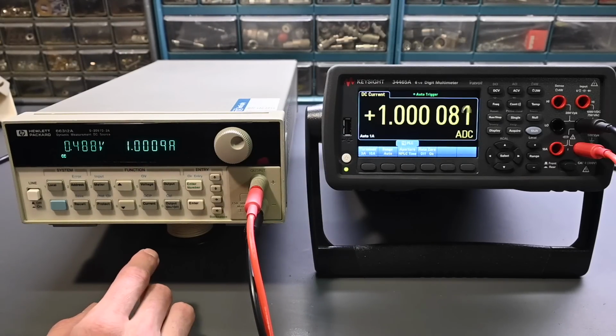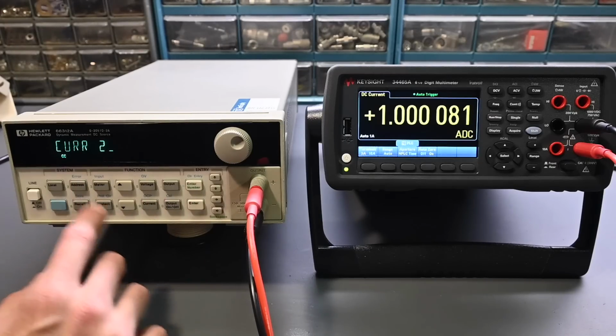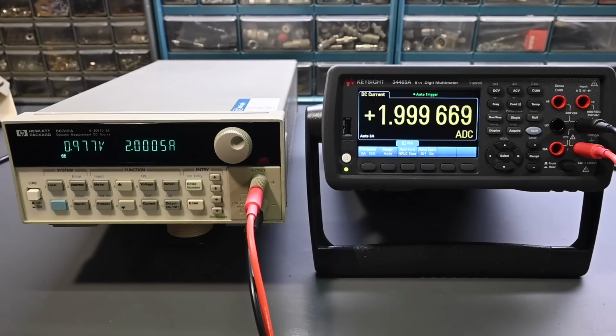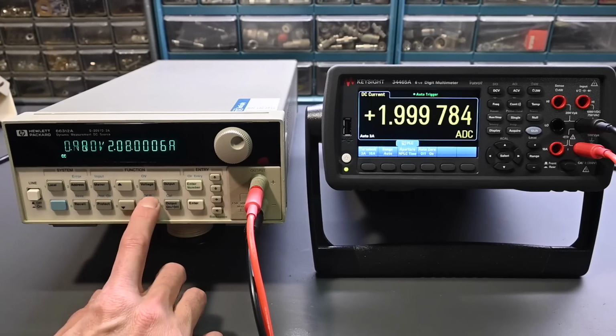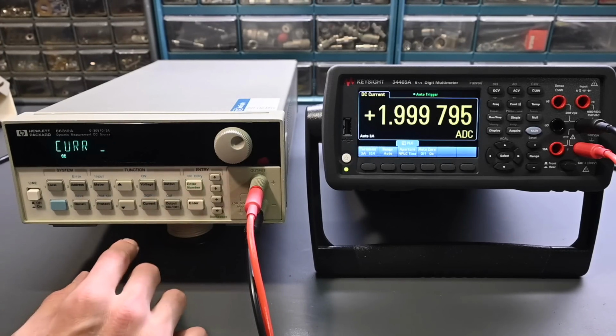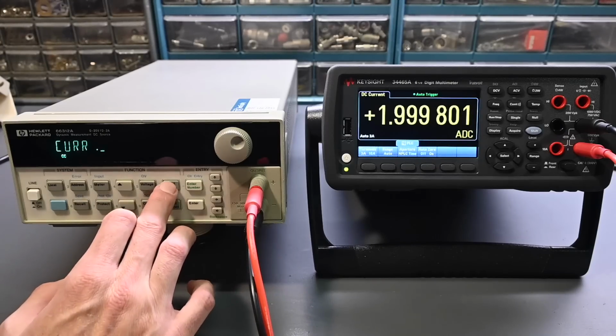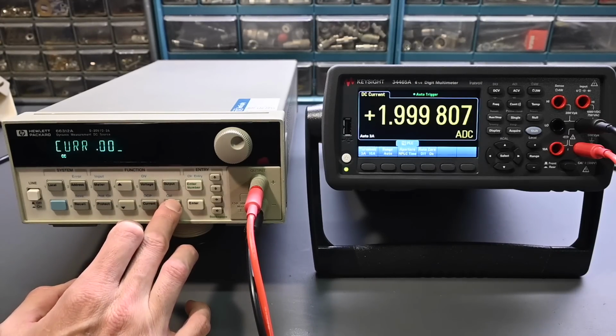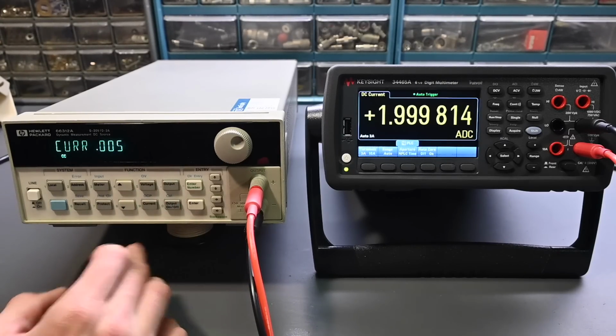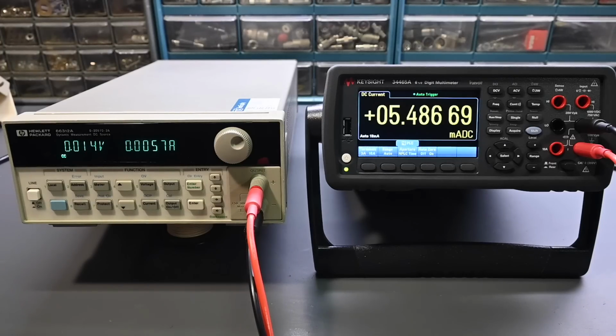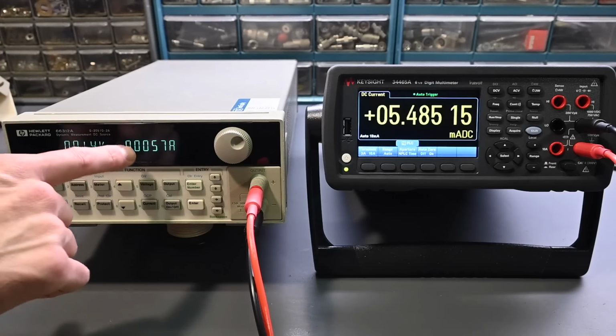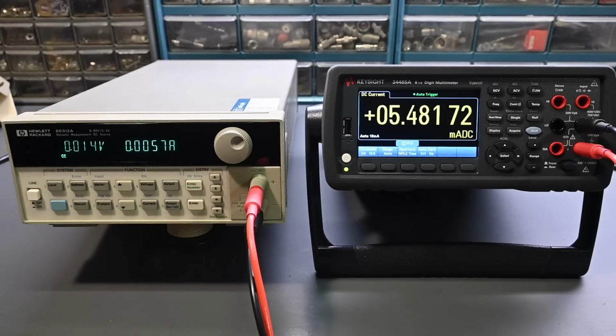Let's go to the full output current. So they say current, enter number 2 amps. And yeah, perfect, no problems there, right at 2 amps. Looks very good. Let's see how the voltage has come up a little bit higher, but still constant current mode. Let's try a really low value of current. So let's say, go to current, and then enter number, let's say 0.005, so 5 milliamps. Yeah, very close. So 5 milliamps there, sitting at 5 milliamps over here.